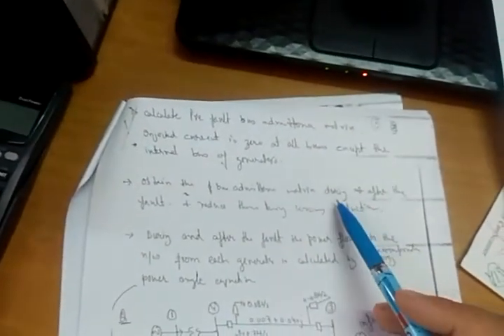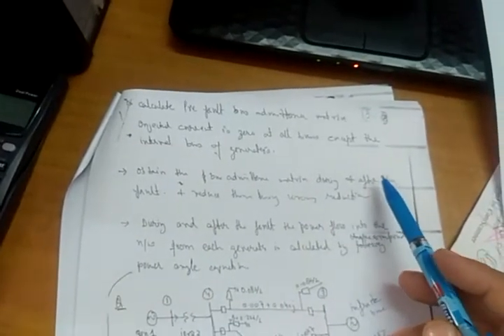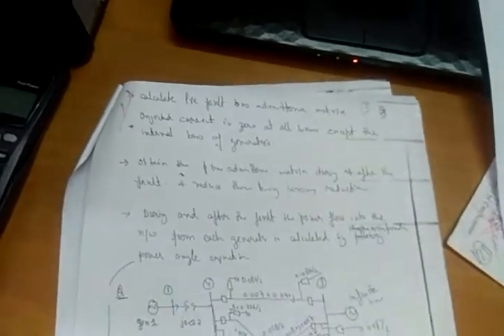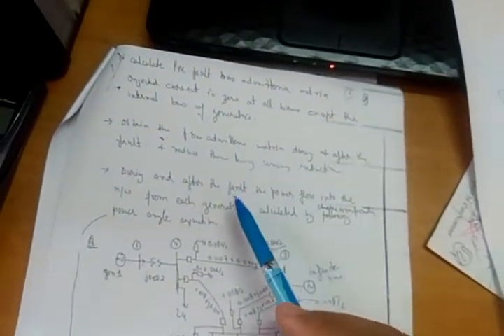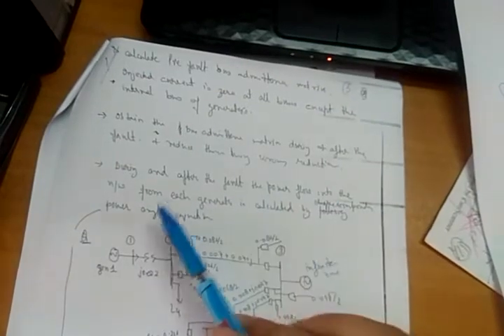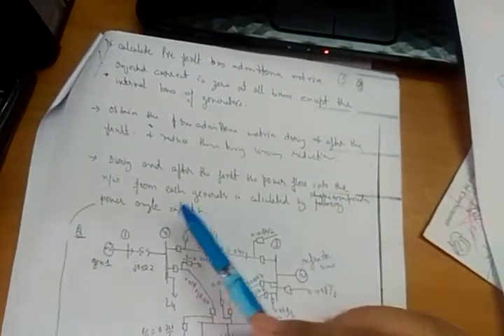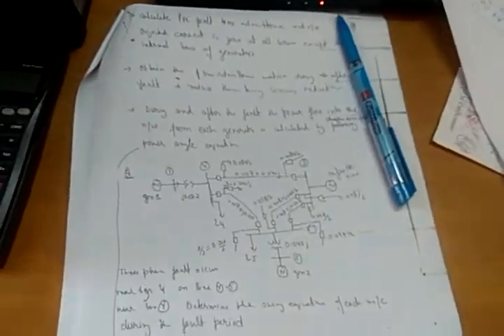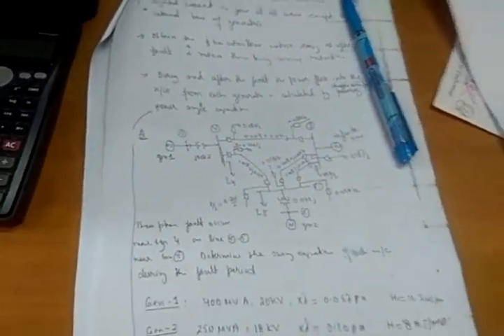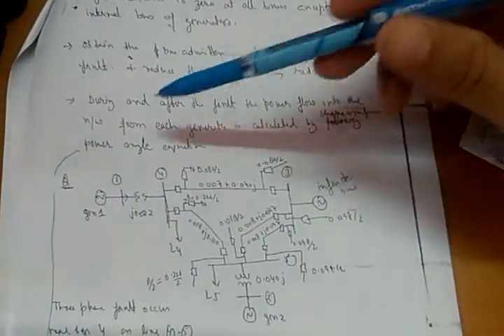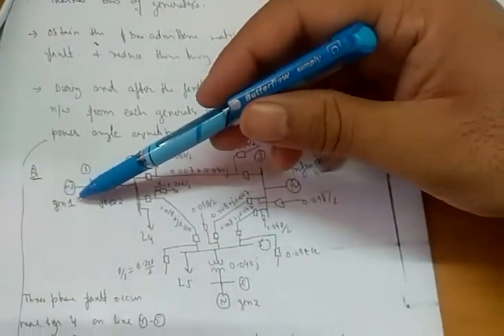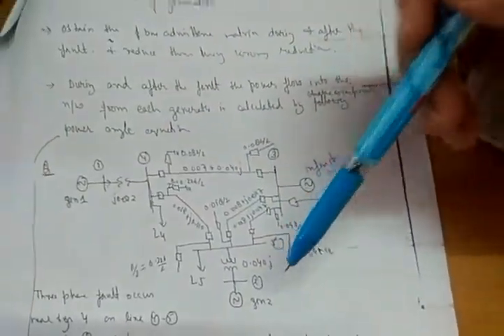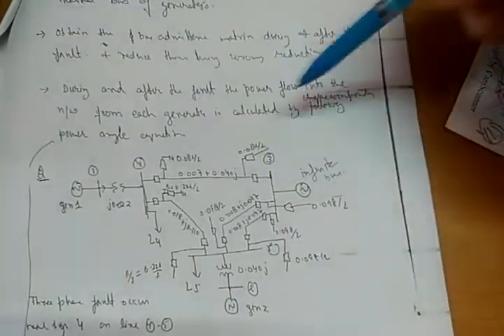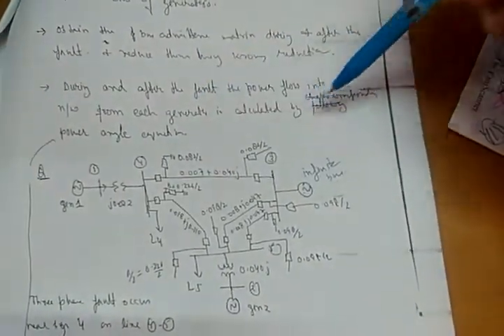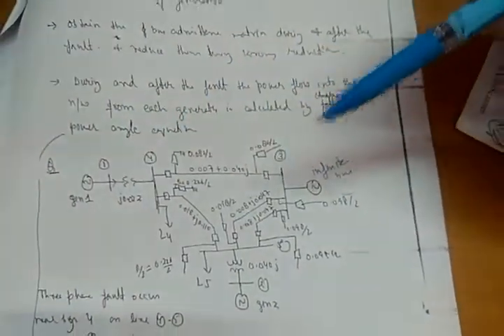So obtain the bus admittance matrix during fault, after fault, and before fault, and reduce them by using Kron's reduction. So during and after the fault, the power flow into the network from each generator is calculated by the corresponding power angle equation, that is, 2H upon omega into d square delta upon dt square is equal to P mechanical minus P electrical. So it is written here, during and after the fault the power flow into the network from each generator, means from generator 1 it will be electrical power 1, from generator 2 it will be electrical power 2. So it is calculated by using the corresponding power angle equation.